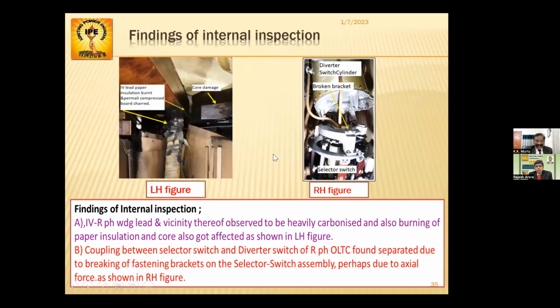So you can see the findings. When the transformer is opened and seen, you can see this. This is the lead of R phase winding, that IV. R phase IV lead. You can see the black end here. The R phase winding lead and vicinity thereof is observed to be heavily carbonized, and also burning of paper insulation, and core also got affected as shown in left hand figure. This is the core. Core is also affected.